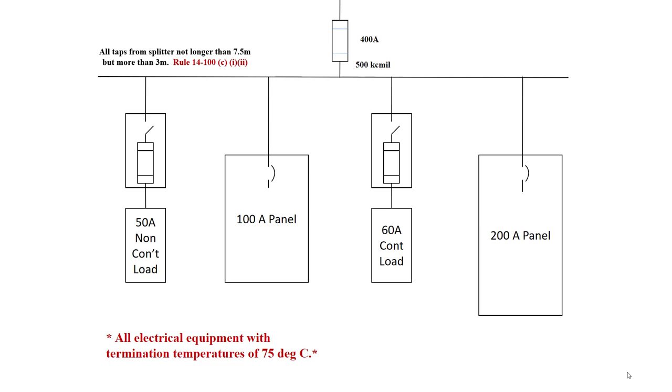Let's read through rule 14-100C and items 1 and 2. It says where the smaller conductor has an ampacity not less than one-third of the larger conductor from which it is supplied. We're dealing with this tap conductor right here that goes to our first fusible disconnect.